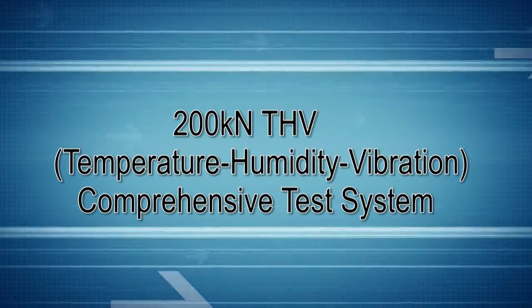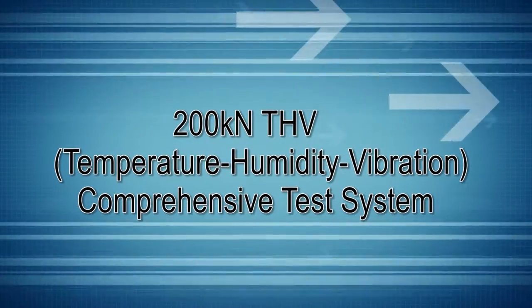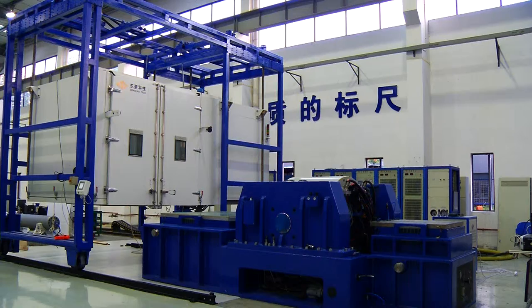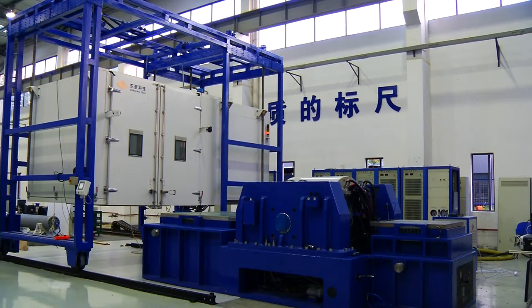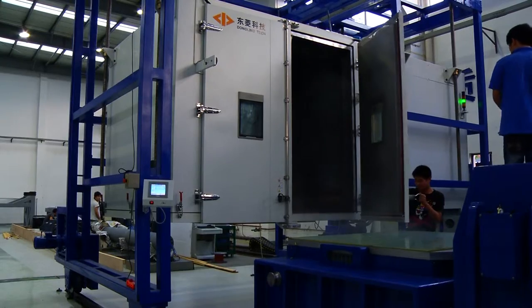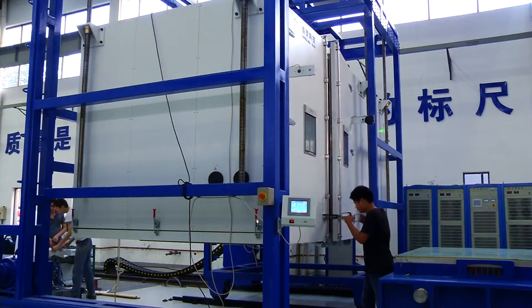200 kN THV Temperature, Humidity, Vibration Comprehensive Test System. This THV system uses 200 kN Electrodynamic vibration shaker and 10 m³ climate chamber to do temperature, humidity, and vibration comprehensive test.